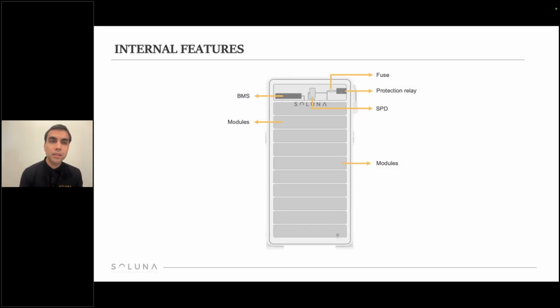The main things about the internal features is that you have multiple layers of safety. Not only the BMS integrated in it, but it also has the SPD, the protection relay, and a fuse. Different from other competitors where they have MOSFET, where the BMS is connected to the MOSFET, and if one cell gets burned, the BMS is in danger. But with the protection relay, you can see how it is physically separated from the BMS. And if there is an issue, the relay will maybe be the one getting burned without compromising the BMS.